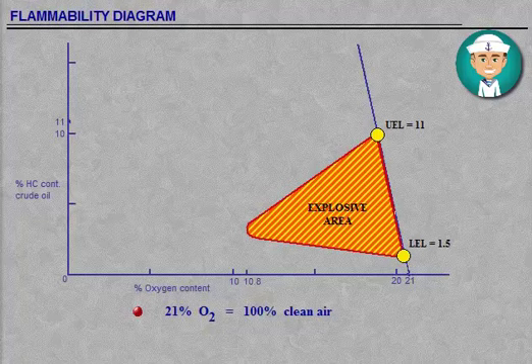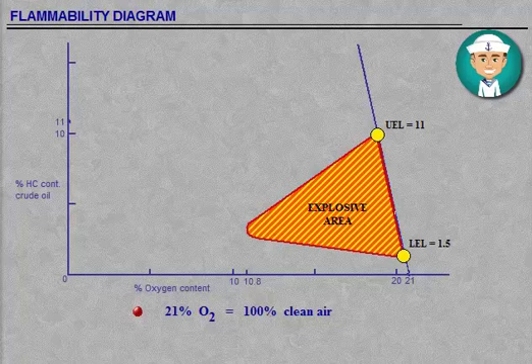Note that 21% oxygen represents 100% clean air and, as previously mentioned, 10.8% by volume of oxygen is the minimum oxygen content to be present to ignite a mixture.